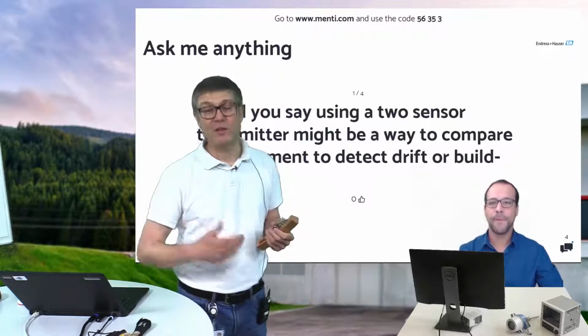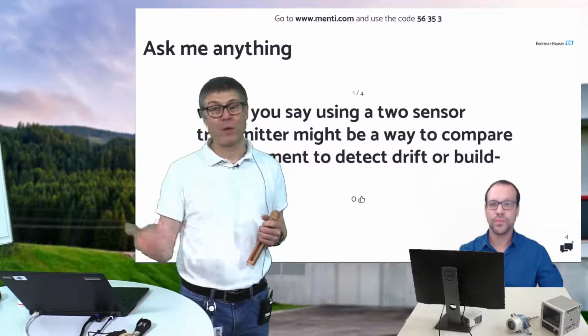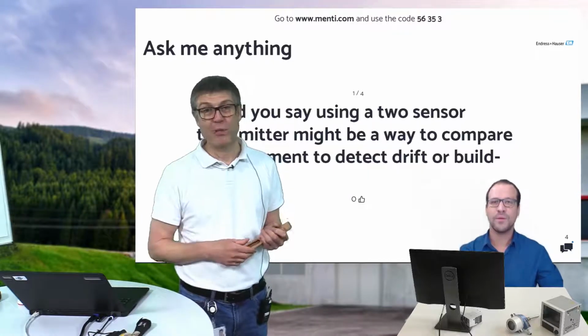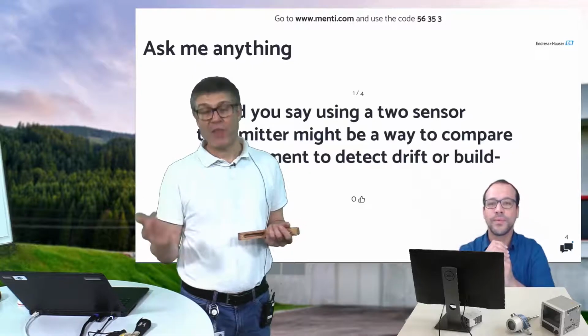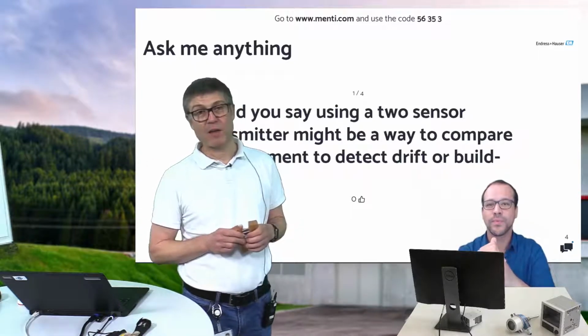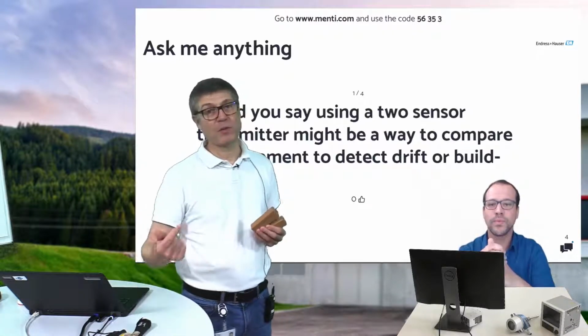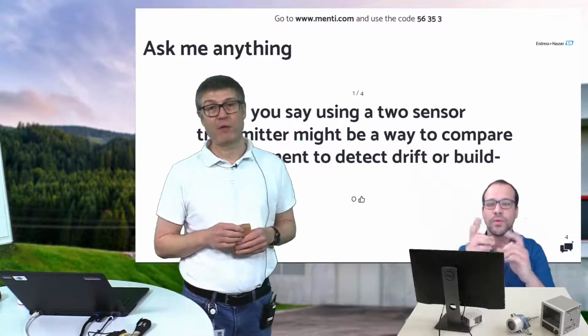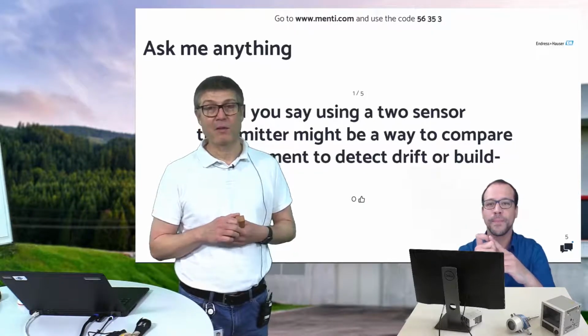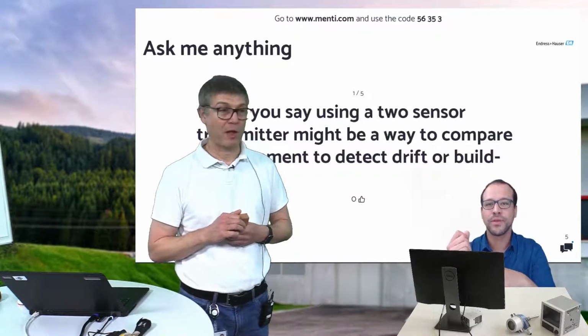Then you need to know how to calculate the CVD values from your calibration results, which is not very easy to do. And then if you enter the field care, device care software with the right DTM, you can tell the transmitters the new CVD values. Yes, it's possible, but it's something for experienced calibration technologists.